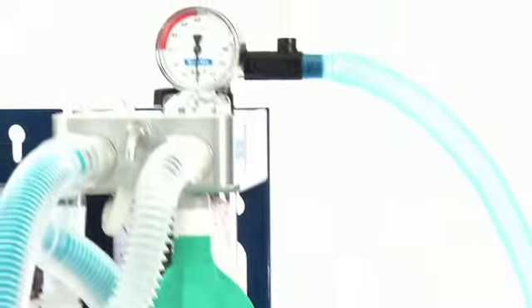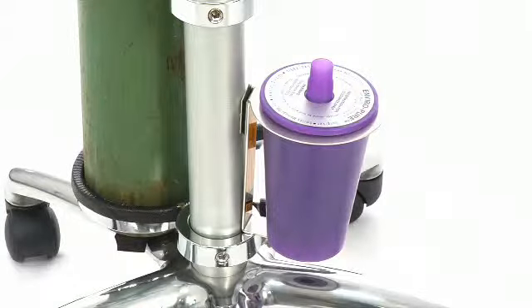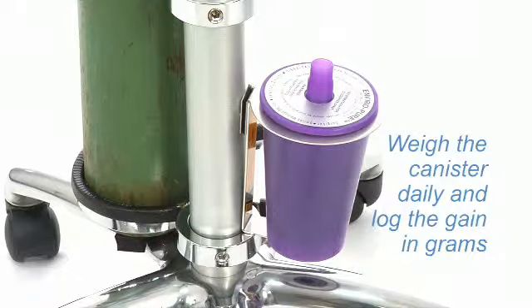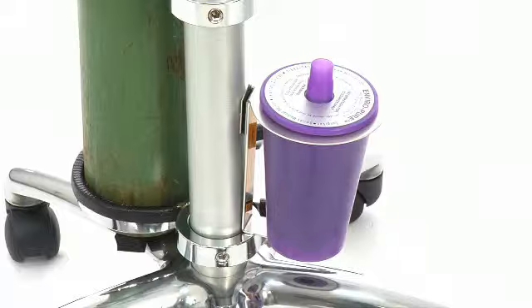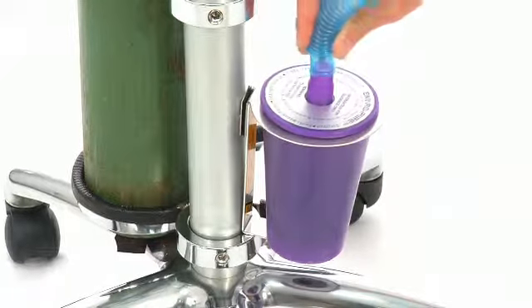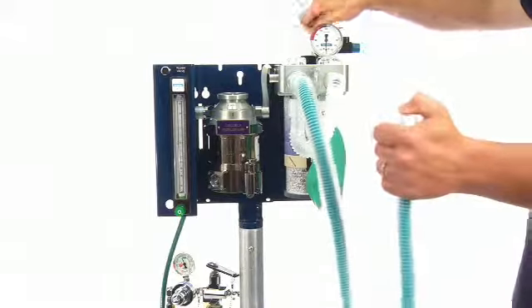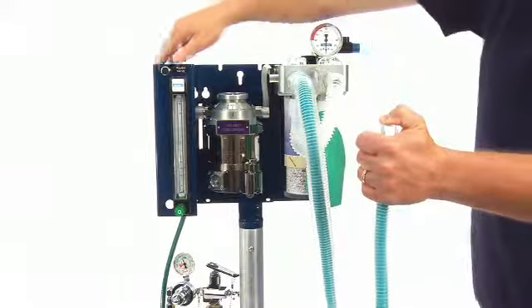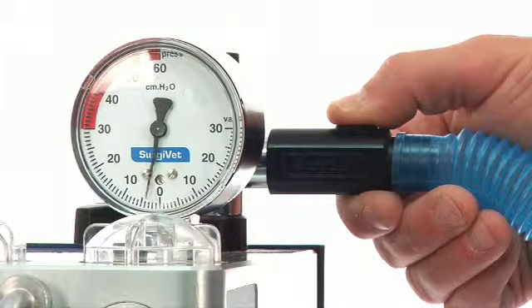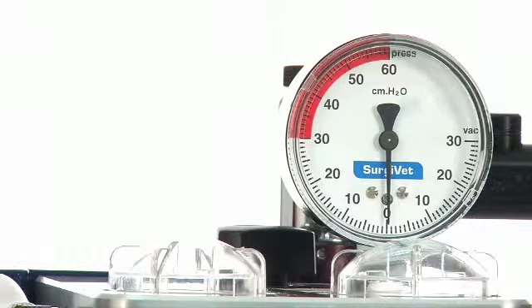The scavenging system should be evaluated daily to ensure proper function. If using the EnviroPure canisters, weigh the canister daily and log the weight gain in grams. Dispose of the canisters according to the manufacturer's directions. Check the integrity of the evacuation tubing by visual inspection and by performing a pressure test on the anesthesia machine. Ensure that the manometer needle moves smoothly and will land at 0.